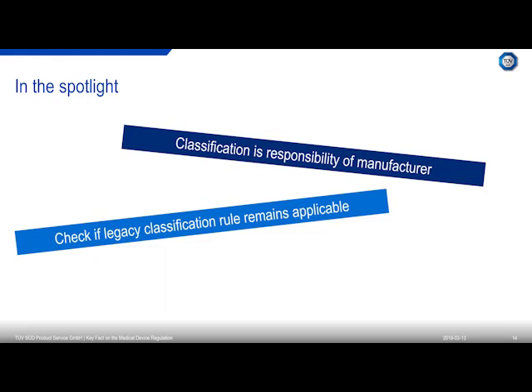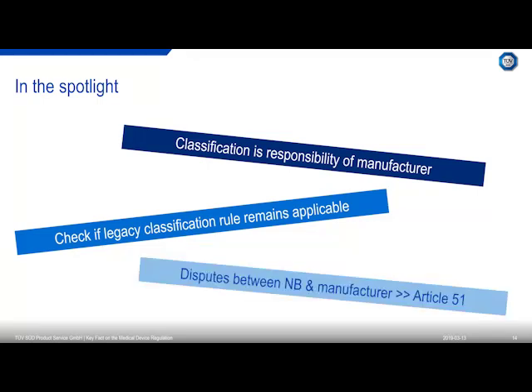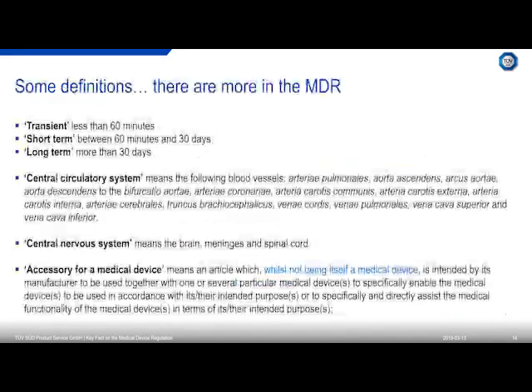You should also check if your current classifications remain applicable, because there will be a lot of up-classifications. There might be some classifications that will be lower than under the current legislation, but mainly what we will see is that a lot of products, specifically in class 2a and 2b, will be classified as class 3 or as class 2b implantables, which is more or less pseudo class 3. And then again, the dispute between notified body and manufacturers is covered in Article 51 of the MDR. As I said, there are some definitions, and I put some on this slide, but I will not go through all of them.